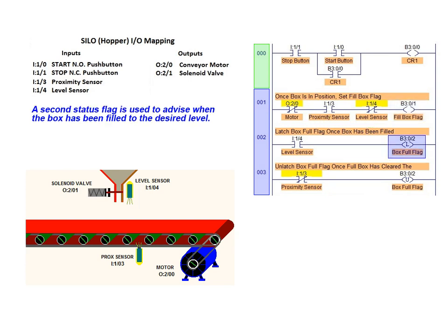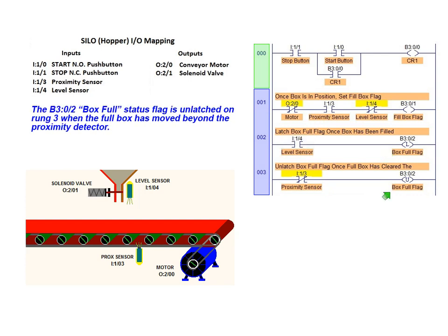A second status flag is used to advise when the box has been filled to the desired level. This status flag uses the bit file address B3 0.2. Rung 2 latches the B3 0.2 bit file status flag when the level sensor is triggered, indicating that a container has been filled to the desired level. The B3 0.2 full box status flag is unlatched on rung 3 when the full box moves beyond the proximity detector.